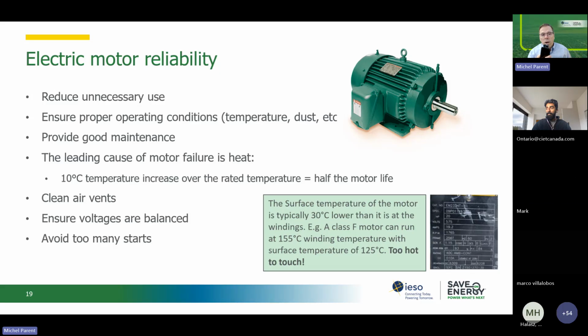So again, I'm going to show you that little infrared camera. If you have that little infrared camera, you could go around very quickly when your motors are running fully loaded, not, if they have a VFD, when they're at 20 hertz. And if you measure a surface temperature that's higher than, let's say, 105 for most spaces, which would be around 20 degrees Celsius, then that motor is likely running too hot. So you do have an issue. Maybe the little fan at the back, the little grill is all plugged, or the space is too hot.